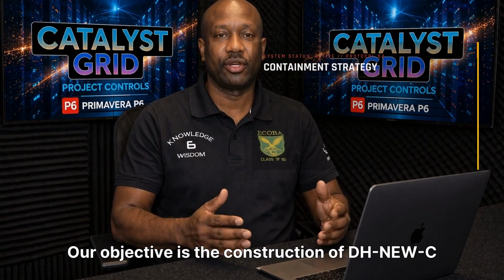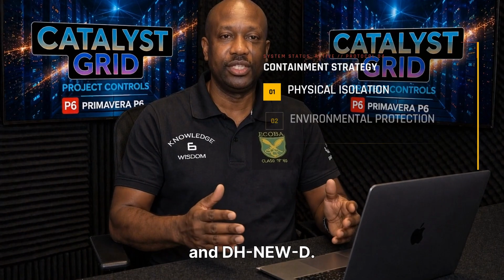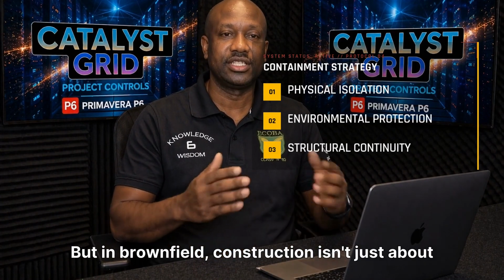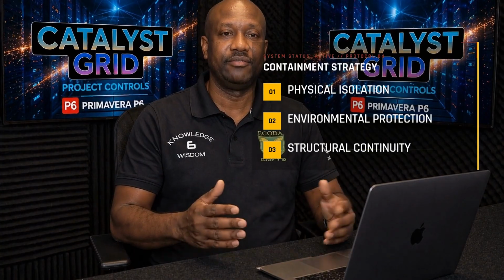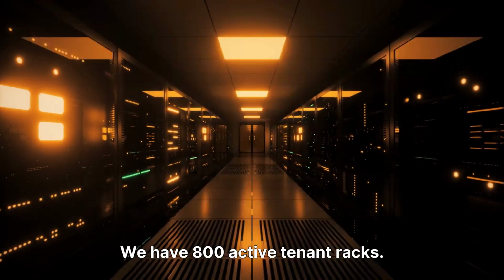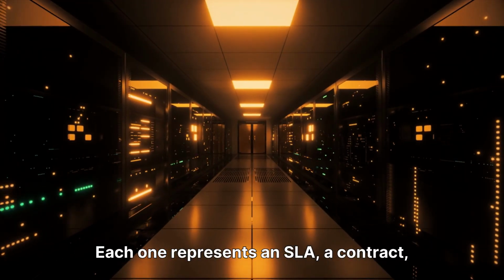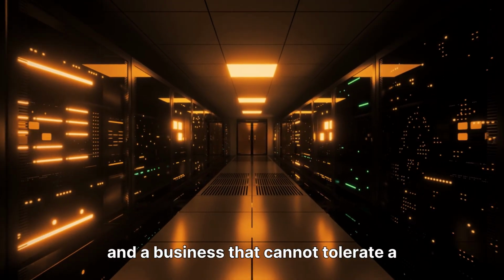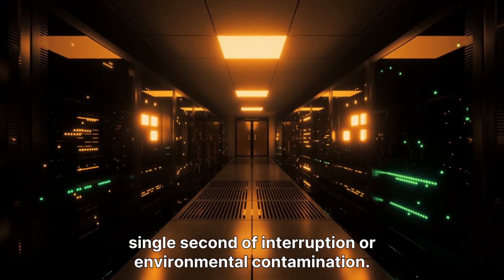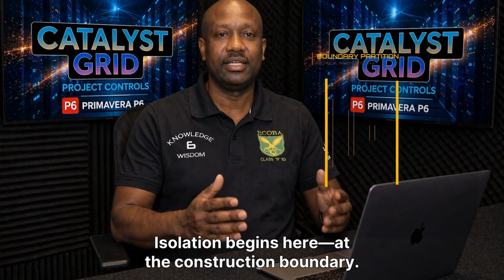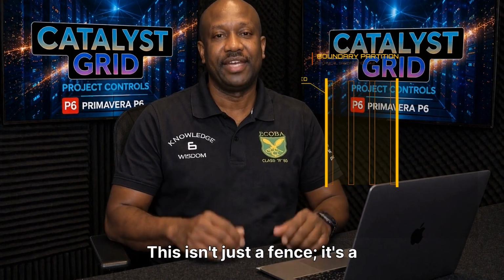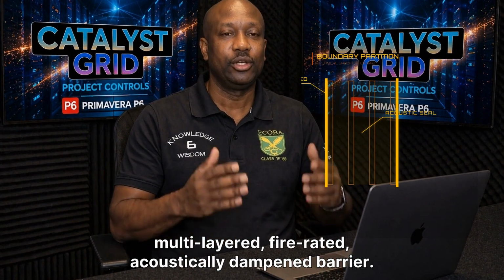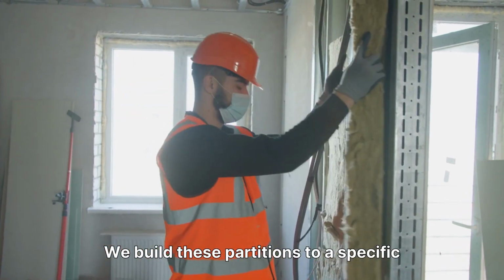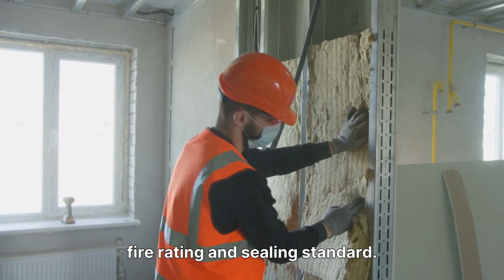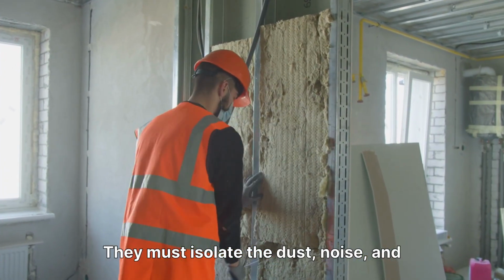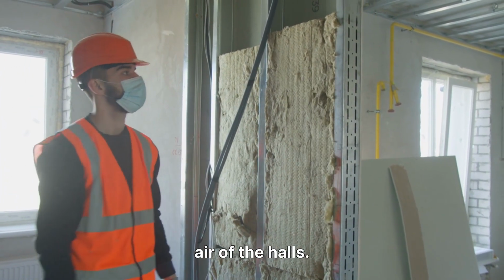Our objective is the construction of DH New C and DH New D. But in brownfield, construction isn't just about building up, it's about containing the impact of every move we make. We have 800 active tenant racks. Each one represents an SLA, a contract, and a business that cannot tolerate a single second of interruption or environmental contamination. Isolation begins here, at the construction boundary. This isn't just a fence, it's a multi-layered, fire-rated, acoustically dampened barrier. We build these partitions to a specific fire rating and sealing standard. They must isolate the dust, noise, and heat of construction from the critical cooling air of the halls.